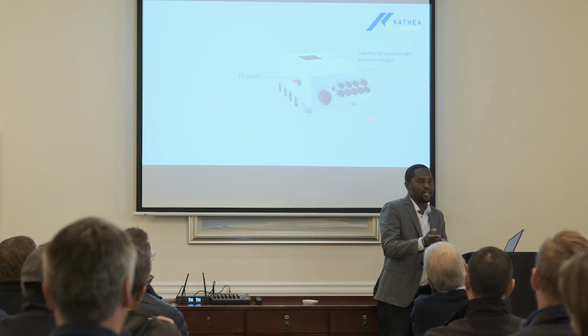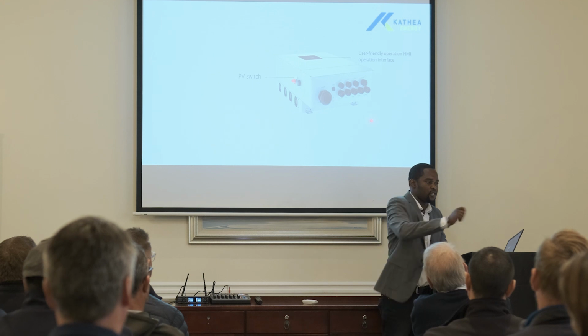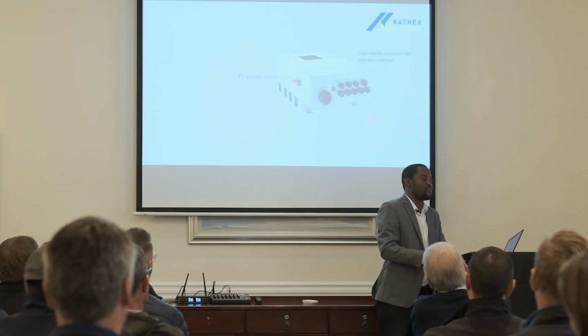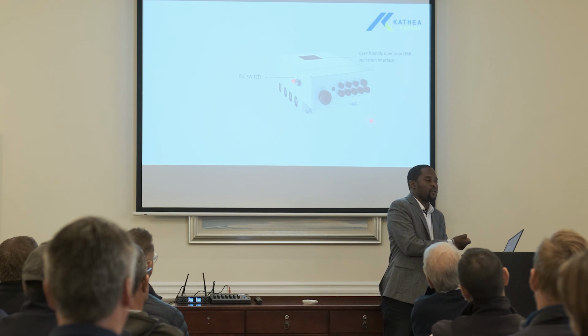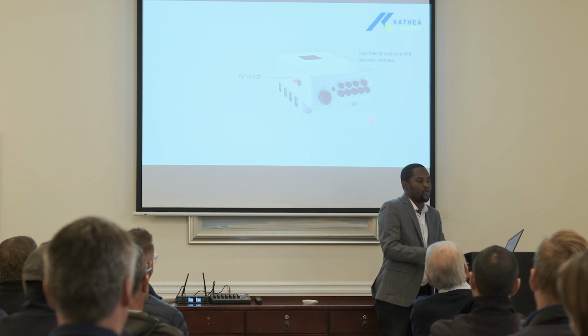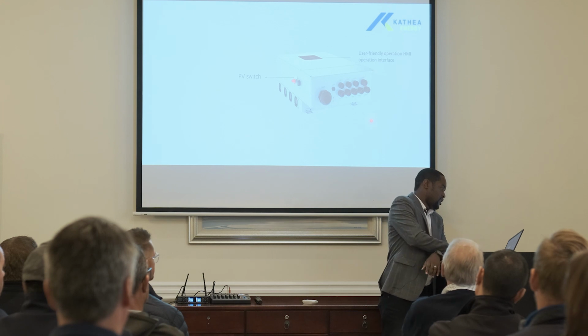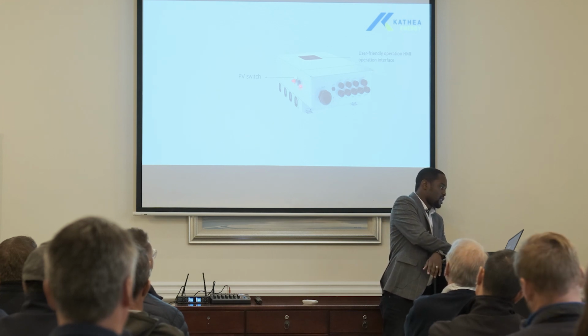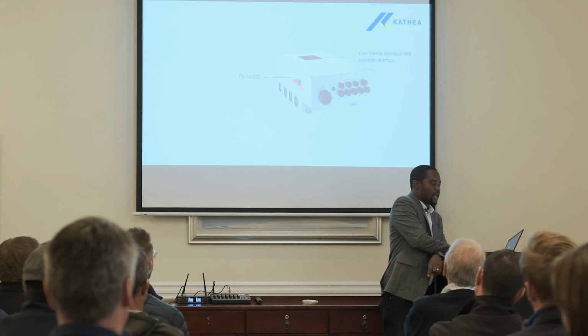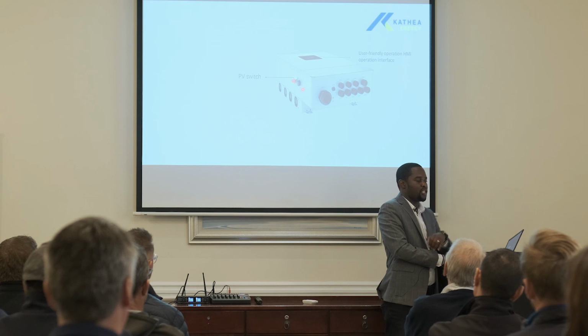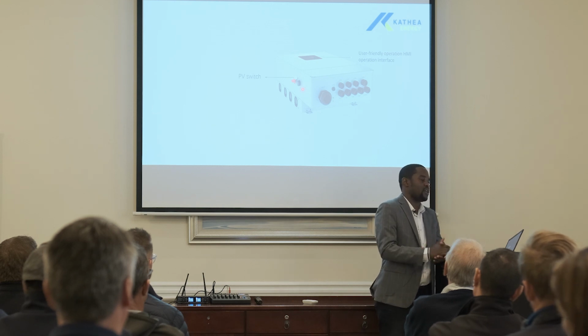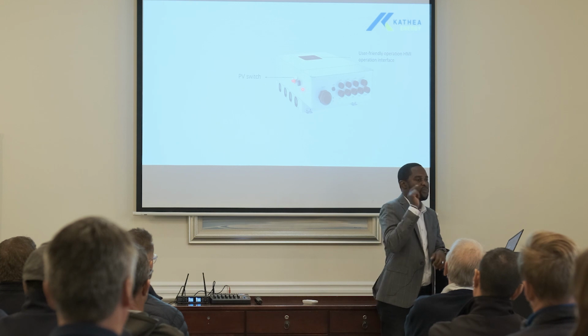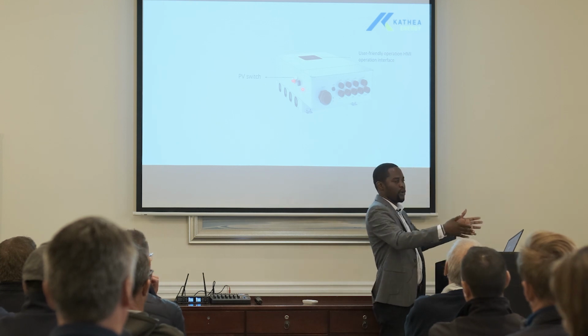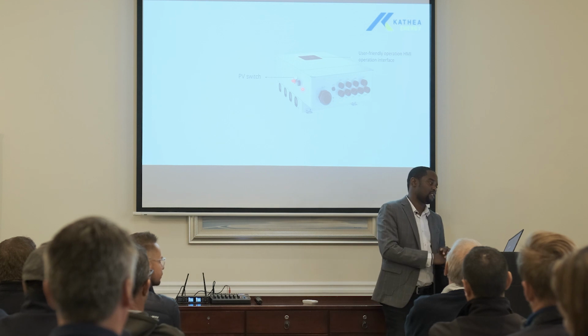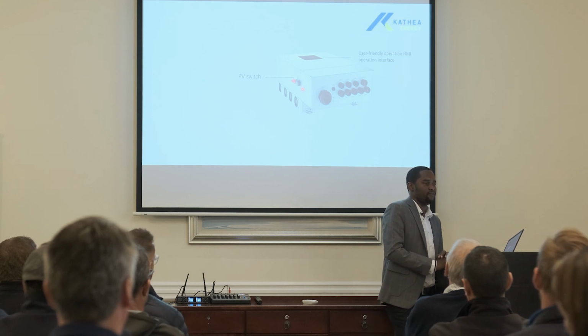But now there can be kids, or someone who might not have information. He wants to switch off, he doesn't know the switch off procedure. So now we have got a padlock, a mechanism to put a padlock there where you can lock now and make sure that no one tampers with that, number one. Then if you look on the side here, we've got a button called an EPS RSD switch, where after making all connections, you need to push that in to start your inverter so that it can be on and starts working. So someone can also come and press that, depending on where you mounted the system. Someone can come and press that without knowing, or playfully if it's kids.